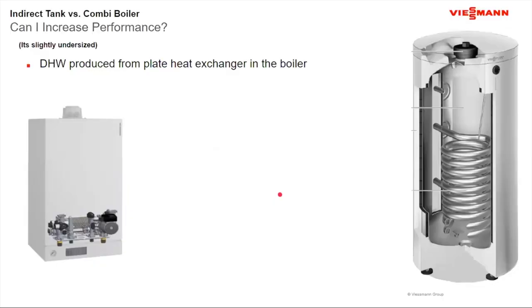Okay. Now, a question came up about this earlier, and unfortunately, I don't have the formula on the tip of my tongue that was asked for, but the question always becomes, what if I come up short? So if I have a combi boiler with a plate heat exchanger, sized exactly for the installation, and somebody says, can I increase the performance? The answer is no. What you get is what you get. So if I have a 199,000 BTU input boiler putting out 180,000, I'm going to get 4.4 gallons per minute at a 90 degree rise, no more. There's no way to extend the performance out.